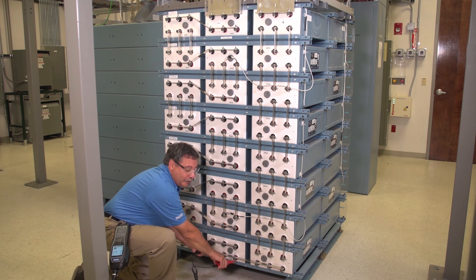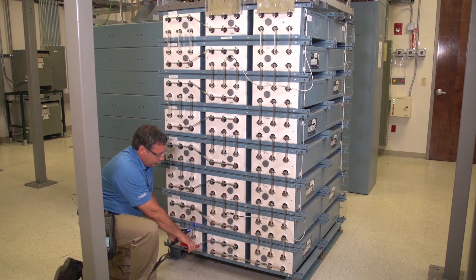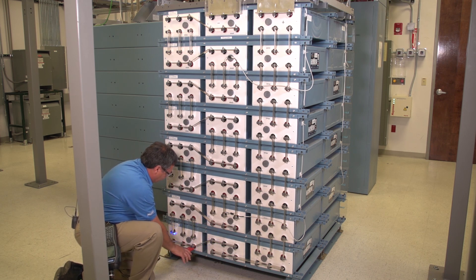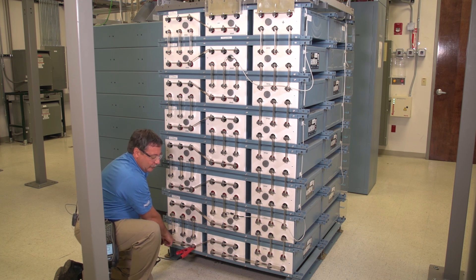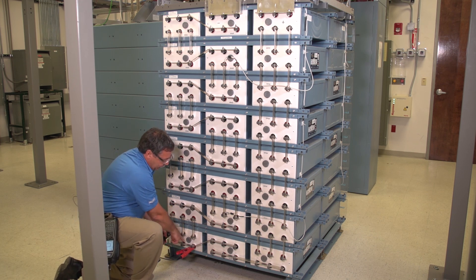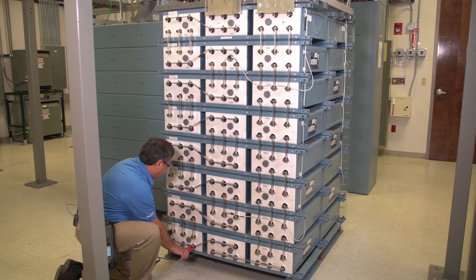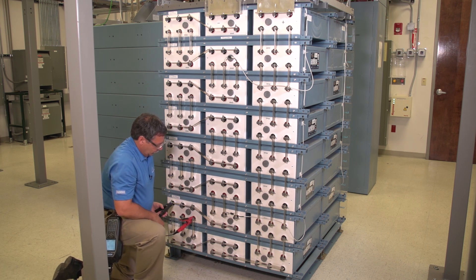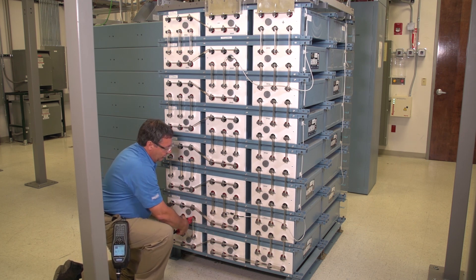What's important here is to follow your inter-cell connectors and make sure you're going in the series connection. I can see this strap is connecting this cell to the next cell — the negatives here to the positives here. Now I'm going up, following that series connection coming over.